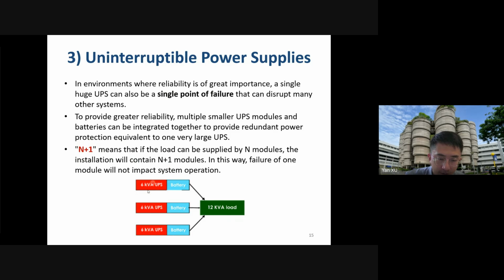But in order to consider the single point failure, for example, there might be a possibility that the UPS module will also fail. There may also be an outage. So in order to consider this single point failure, we need to add one more reserve. We need to add one more redundancy. So it's called N plus 1. The 1 means the additional module as a redundancy, so that even during this UPS power supply condition, if one module is out, we can still supply the full load. So that is some design criteria for the UPS power supply.